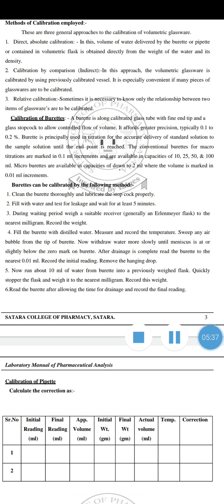The burette can be calibrated by the following method. Clean the burette and lubricate the stopcock properly, then fill with water and test for leakage, waiting at least 5 minutes. During the waiting period, weigh a suitable receiver to the nearest milligram and record the weight. Then fill the burette with distilled water, measure and record the temperature, and sweep any air bubble from the tip of the burette. Now withdraw water slowly until the meniscus is at or slightly below the zero mark. After drainage is complete, read the burette to the nearest 0.01 ml, record the initial reading and remove the hanging drop. Now run about 10 ml of water from the burette into the previously weighed flask. Quickly stopper the flask and weigh to the nearest milligram. Record this weight. Then read the burette after allowing time for drainage and record the final reading.